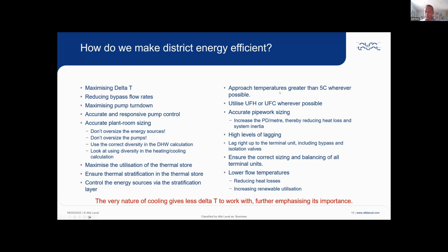And we need to think, when we look at the plate heat exchangers, we need to look at the approach temperatures across those plates, because the approach temperature is simply the temperature difference between the flow in on the primary side and the flow out on the secondary side. That's the approach. The narrower that angle is, so the lower the degrees between the two, the higher flow rates we need, and generally the higher the return will be if it's heating, or the lower it will be if it's cooling. That obviously then decreases the delta T, which we've just understood is a bad way of doing things.